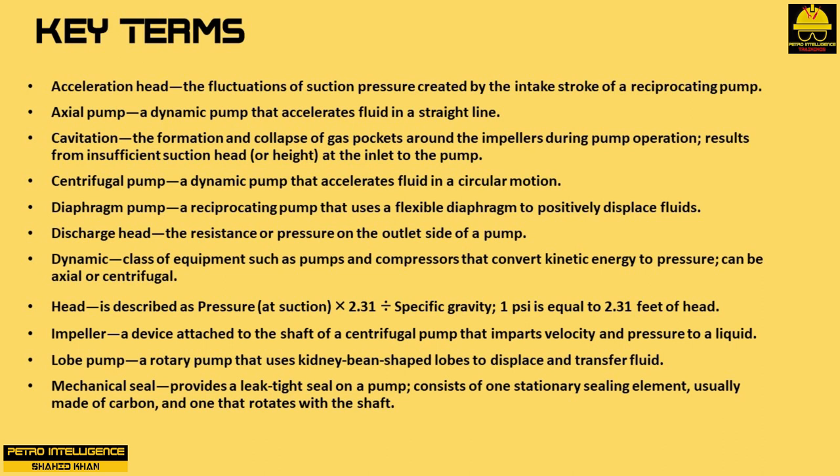Diaphragm pump is a reciprocating pump that uses a flexible diaphragm to positively displace fluids. Discharge head is the resistance or pressure on the outlet side of a pump. Dynamic is a class of equipment such as pumps and compressors that convert kinetic energy to pressure, and can be axial or centrifugal. Head is described as pressure at suction times 2.31 divided by specific gravity; 1 psi is equal to 2.31 feet of head.